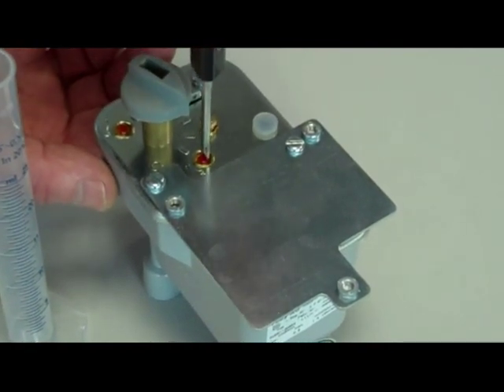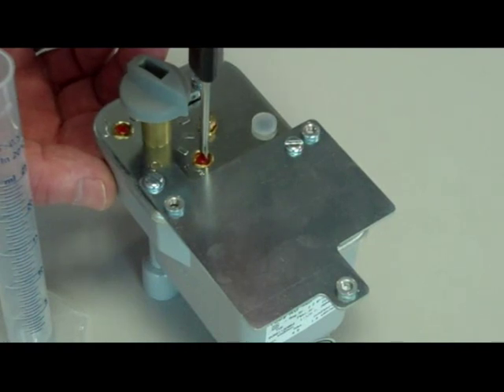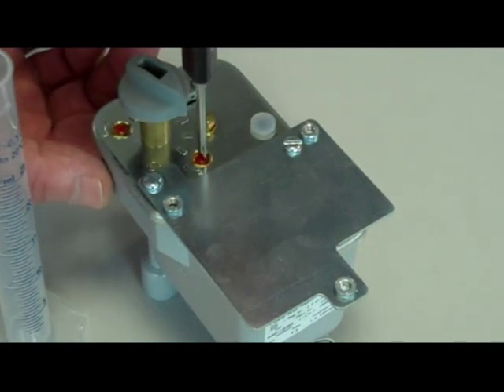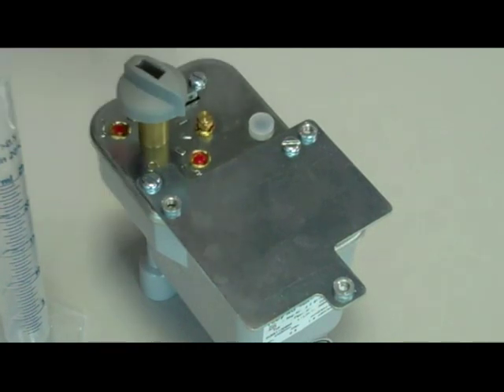Again, just adjust the low fire screw if necessary. Screw clockwise to reduce the oil rate and anti-clockwise to increase the oil rate. No more than a quarter of a turn should be necessary.